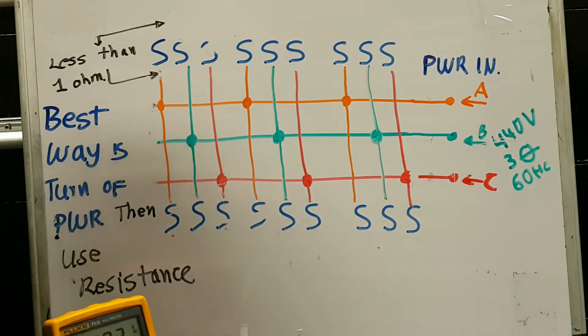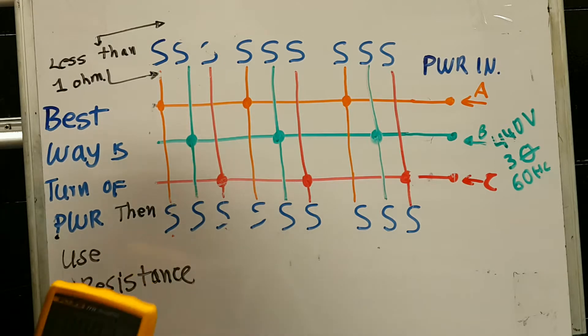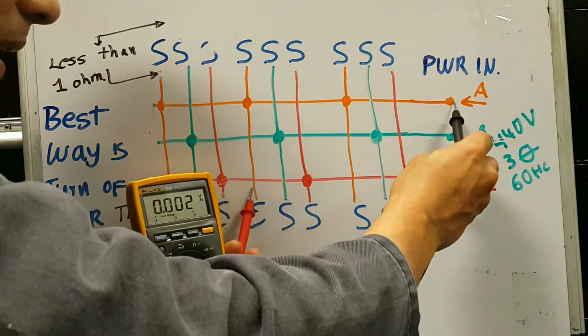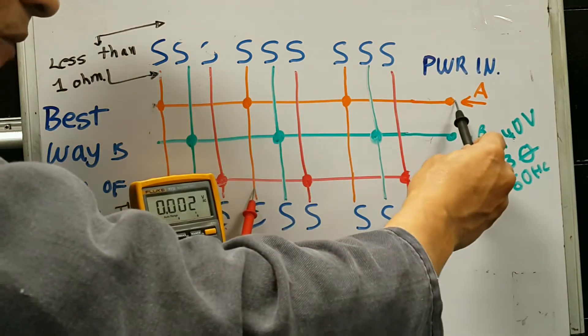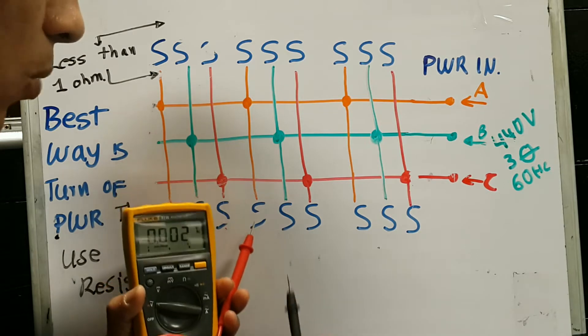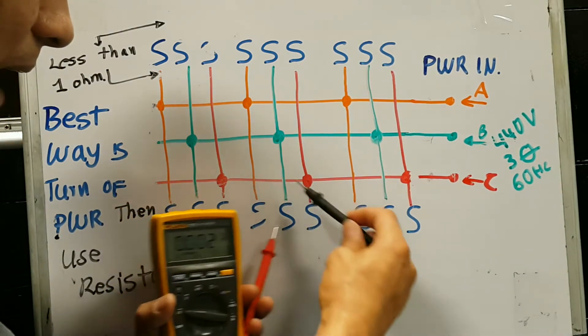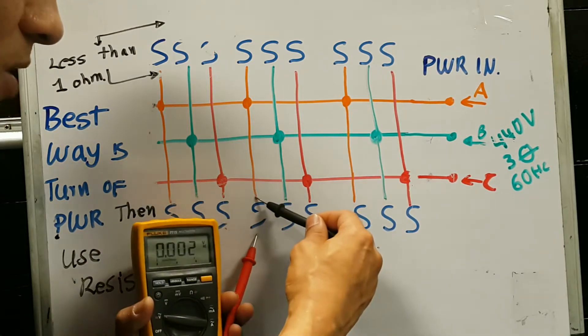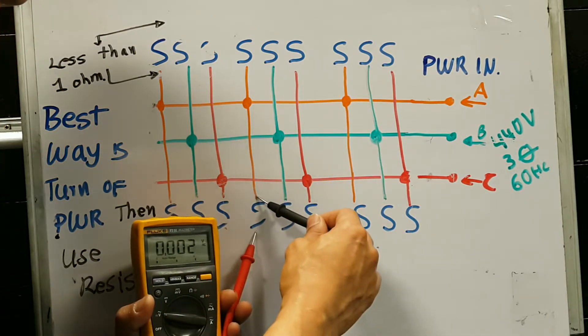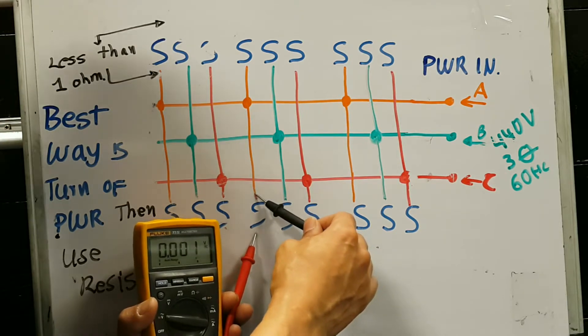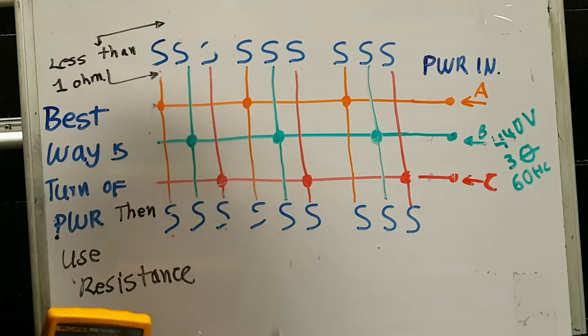Now, top to bottom is the same thing as I told you before, the difference of potential of the same piece of wire is zero volts. This over here is connected to that. If this is the same piece of wire, the difference of potential in this same wire is zero volts. A fuse is just a piece of wire. So, across it, a good fuse should be zero volts. This one, since it's open, you will get some random voltage. It could be as high as 10 volts or 20 volts or 150 or 200. Anyway, it's not zero. Therefore, that would be a bad fuse.